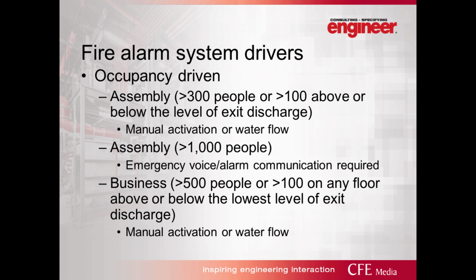Now, the fire alarm system drivers are actually a little different than sprinklers, right? So they don't mesh up, right? So, we oftentimes hear people say, well, sprinklers aren't necessarily life safety. Well, in a lot of cases they are. In most occupancies, particularly if you have a light hazard, with 13 we consider light hazards, so office spaces, things of that nature. Those are light hazard. Residential quick response sprinklers are required.